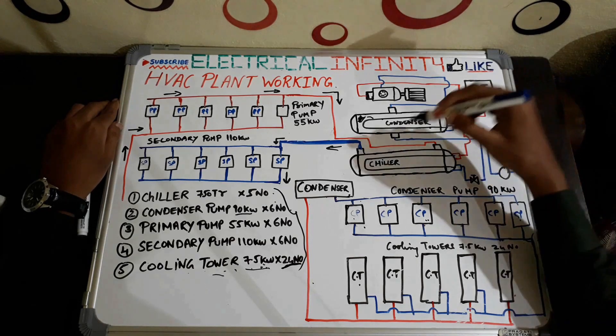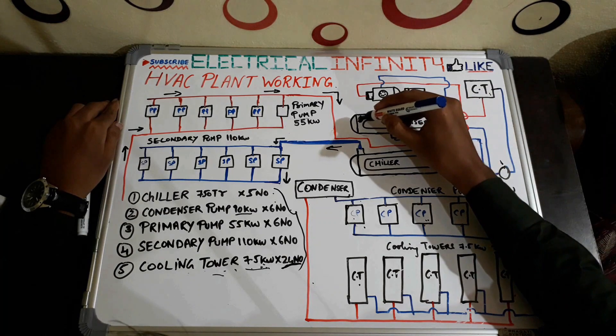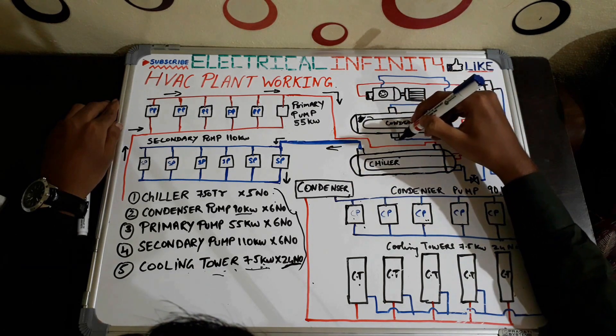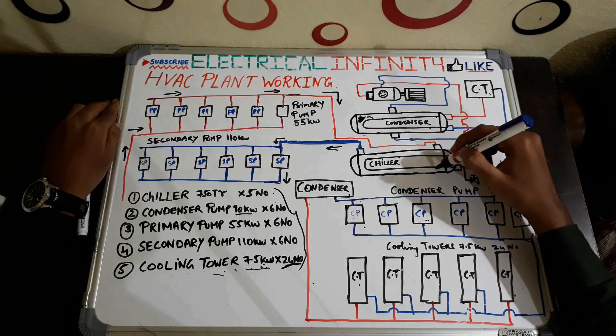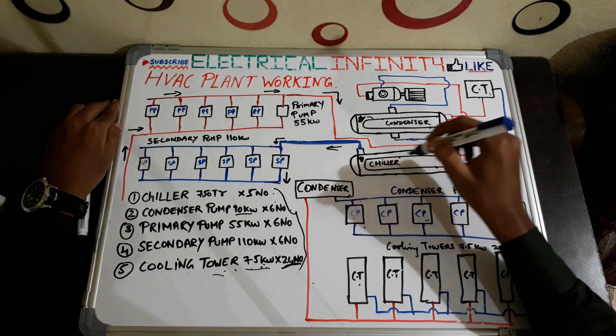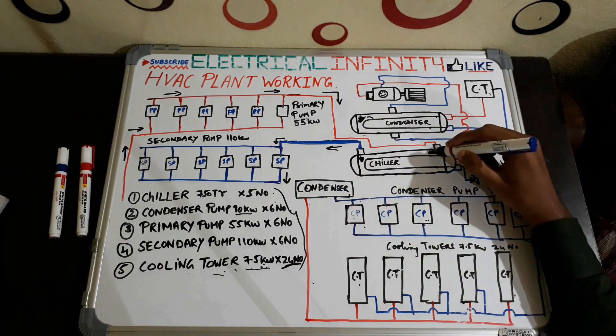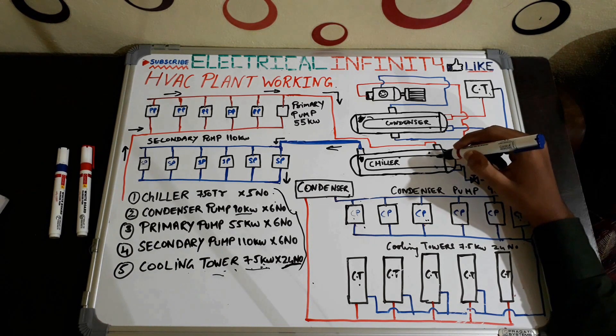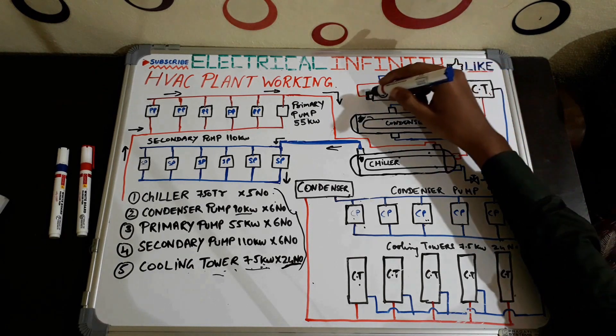Coming to the chiller — the refrigerant is present in the tube type of the chiller, whereas in the condenser it was in the shell type. The refrigerant is transferred from the condenser via an expansion valve into the tube type of the chiller. The water used for cooling the entire building is present in the shell type of the chiller. The water in the shell side gets cooled due to heat transfer with the refrigerant in the tube side. After heat transfer, the warmed refrigerant is sent back to the compressor.